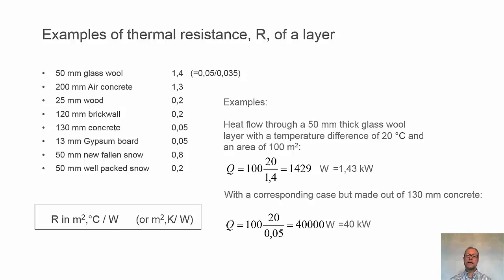Using the formula from the previous slide, Q equals 100 times 20, 100 is the area, 20 is the temperature difference, divided by the thermal resistance 1.4, and we get 1429 watts or 1.43 kilowatts.